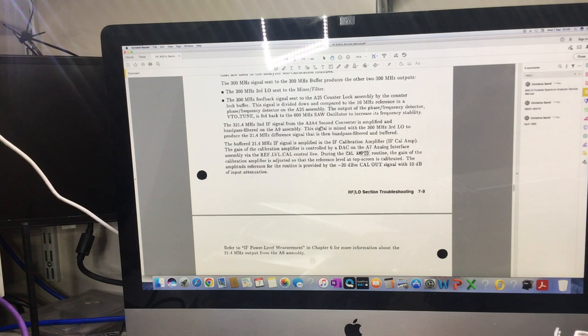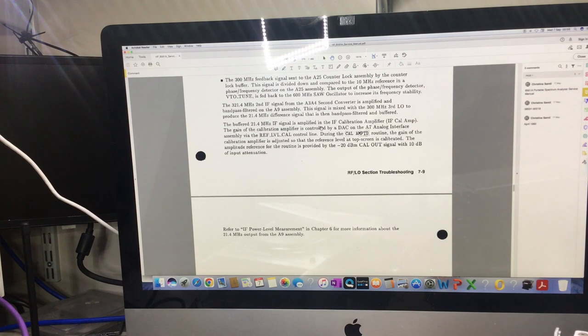300 MHz third local oscillator sent to the mixer filter. Feedback signal sent, that's the one we're looking at now on J3, I believe, to the A25 counter lock assembly, the counter lock buffer. The signal is divided down and compared with the 10 MHz reference in a phase frequency detector on the A25 assembly. The output of the phase frequency detector, VTO_tune, is fed back to the 600 MHz surface acoustic wave oscillator to increase its frequency stability.